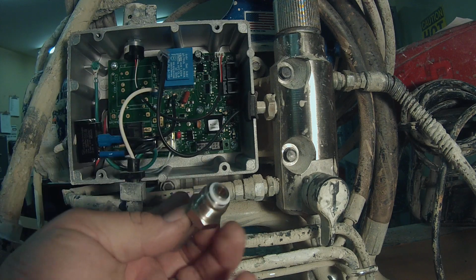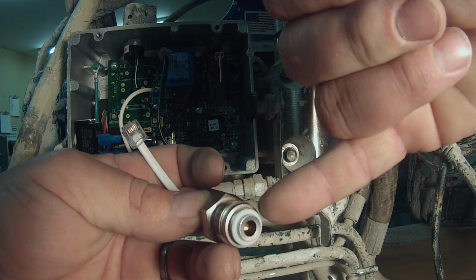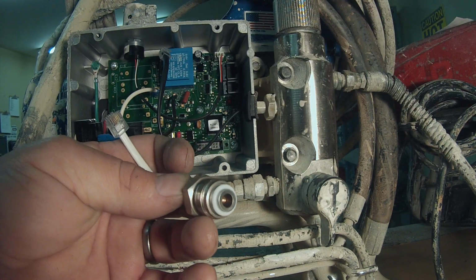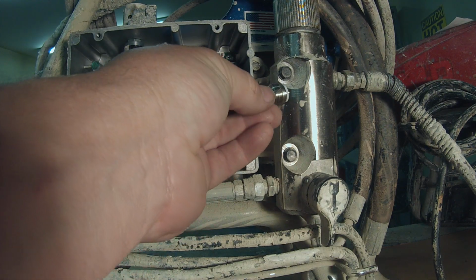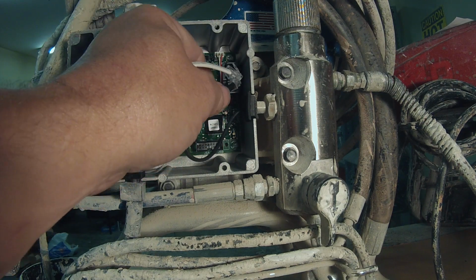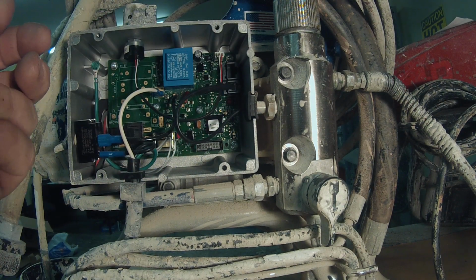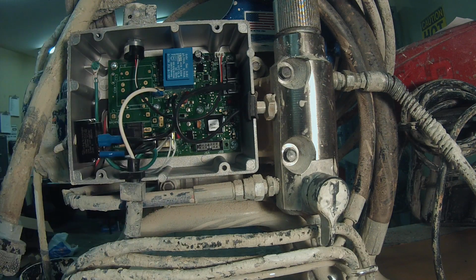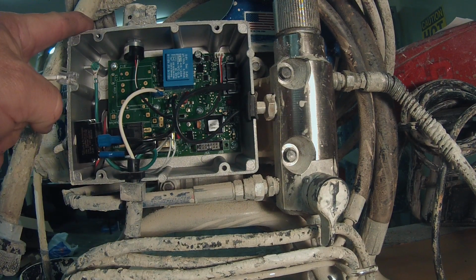So when you take the old one out, look at it, make sure the gasket comes out with the old one, put the new one in, thread it in, get it good and tight, and you'll plug this item. You'll just stick it in the hole and it'll pop right back in, just like that. That's it. That's all it takes to replace the transducer on the Gracos.